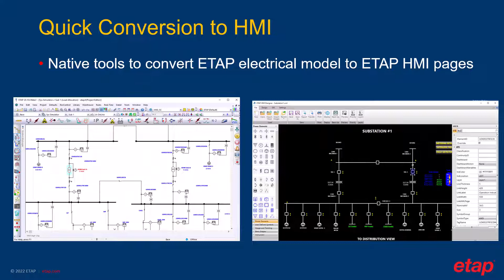Another major advantage is the drastic reduction in the number of animations and calculation tags required, particularly the animations needed to display the correct color for energization. By using the ETAP model, the ETAP HMI engine uses the same switching device continuity coloring just like ETAP. Therefore, if an element is energized, it will also show energized on the HMI automatically.